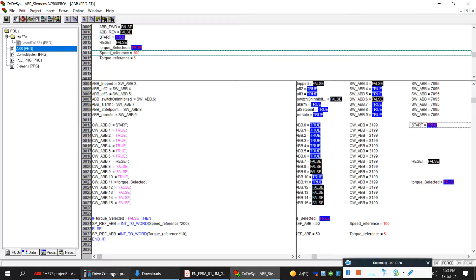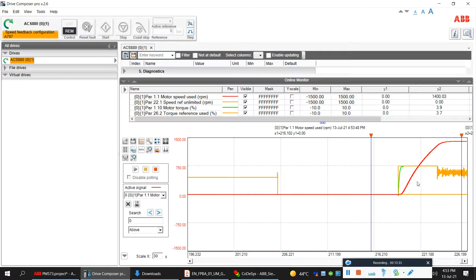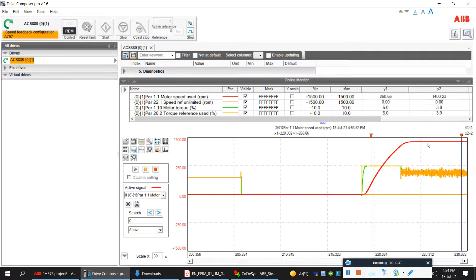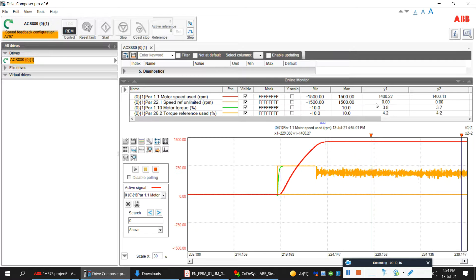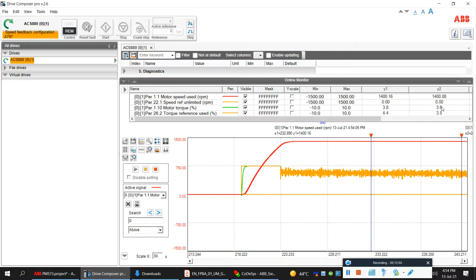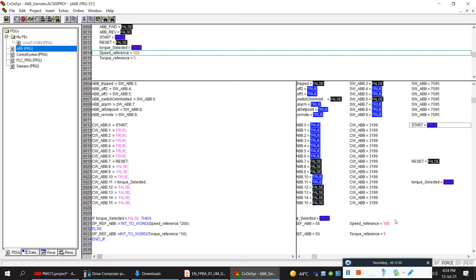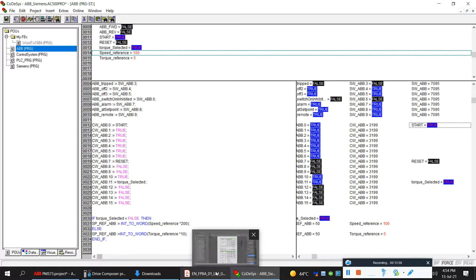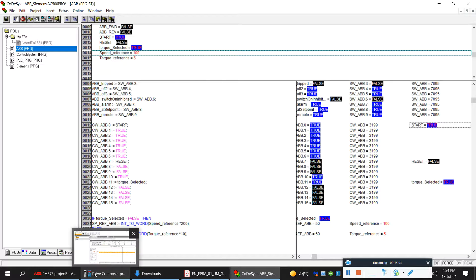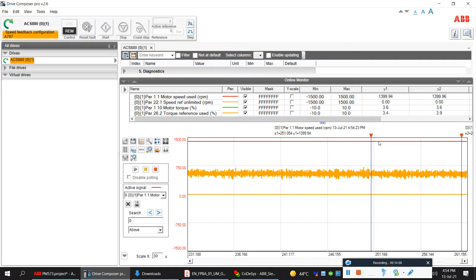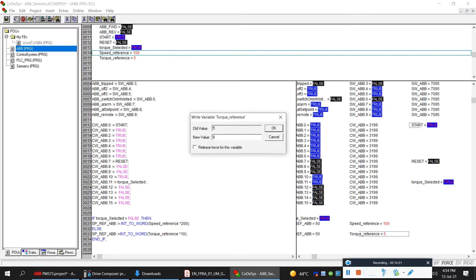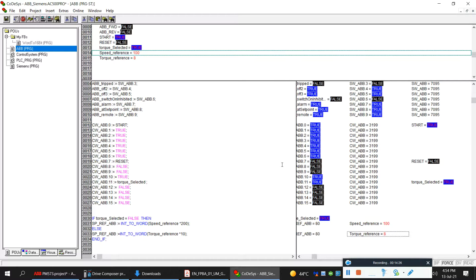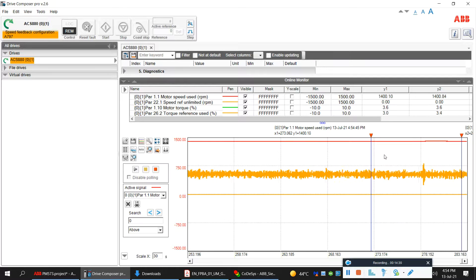This time the motor runs because to generate five percent torque the motor will run at any RPM — its target is to achieve five percent torque. But as you can see, since the motor is completely free, the actual torque generated is only 3.7 percent while my requirement is five percent. So the motor tries its best to reach the target by running at full speed. As the maximum speed is reached and the torque target is still not achieved, let's now give eight percent torque reference.